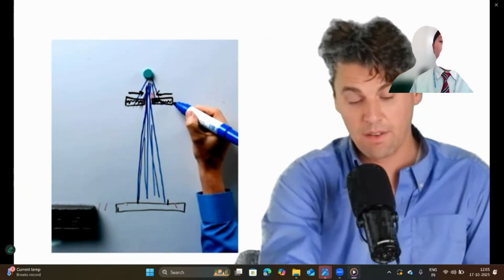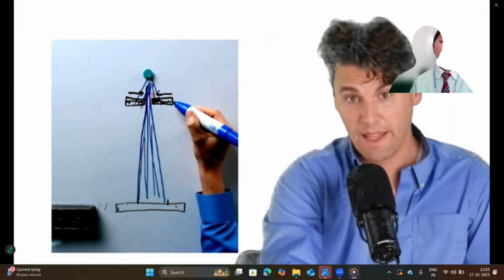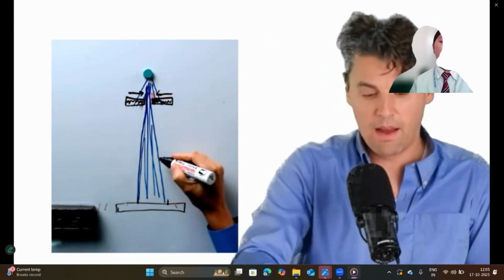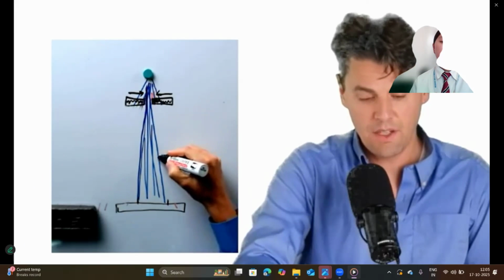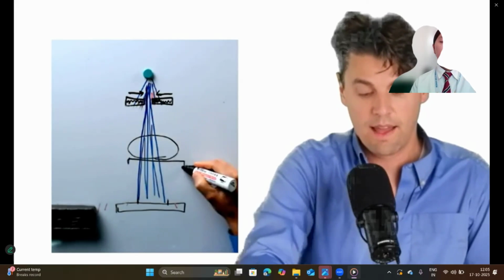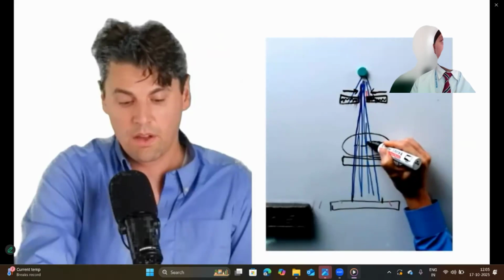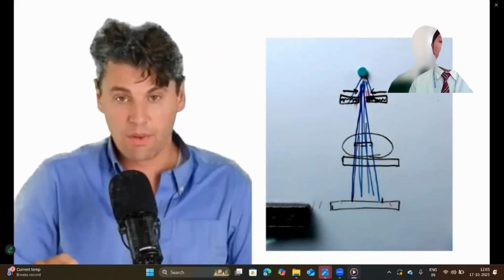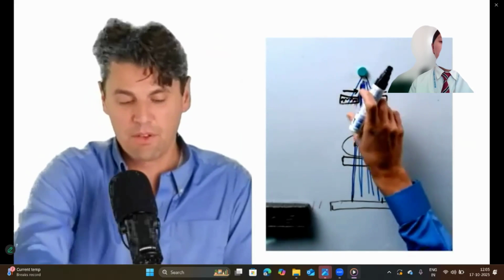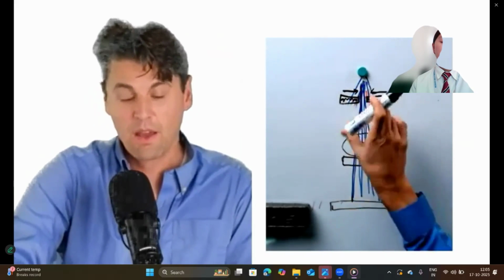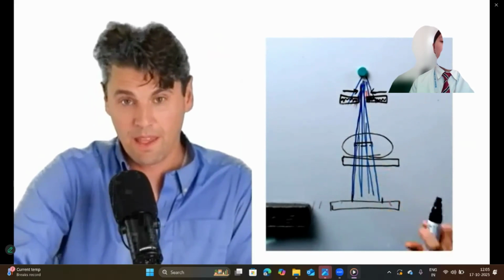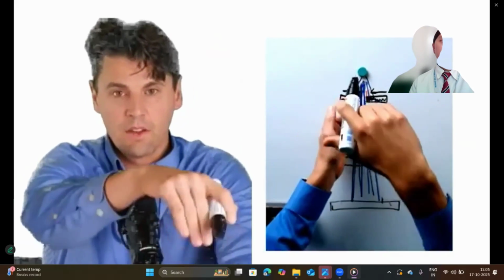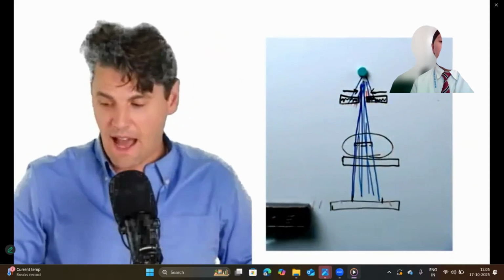So the collimator is defined in a plane that's relatively close to the tube. And then what we often care about is we have a patient that's right in here, lying on a table. We could talk about this here being the field of view in terms of the collimation. I'm only drawing a picture here in 2 dimensions. This is a 3-dimensional case. So we actually have collimators coming this way, and then also collimators coming in and out of the board.